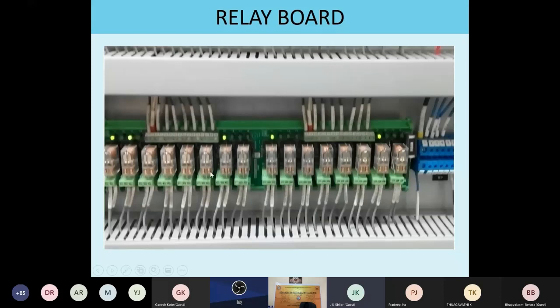And what is the function of the relay board? The relay board function is, suppose the PLC output is 24 volt, but a motor is required to run at 230 volt. So the PLC will give 24 volt to the relay to pick up, but the relay output we have connected to 230 volt. If this respective relay picks up, then 230 volt extends to the field side.